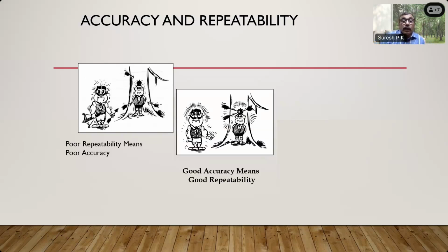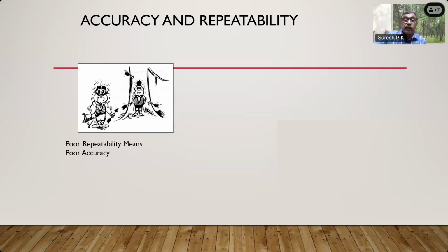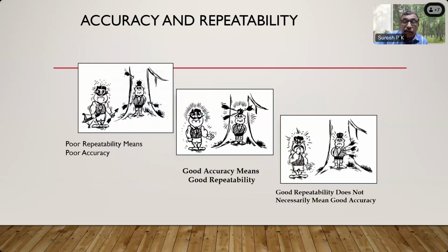This is good accuracy, good accuracy and good repeatability. So good accuracy means good repeatability, definitely. But good repeatability does not necessarily mean good accuracy. It shows always the wrong reading, but you are getting good repeatability, but it is not accurate. So poor repeatability is definitely poor accuracy. Good accuracy always produces good repeatability. Good repeatability does not necessarily mean good accuracy. It can sometimes be not accurate also.